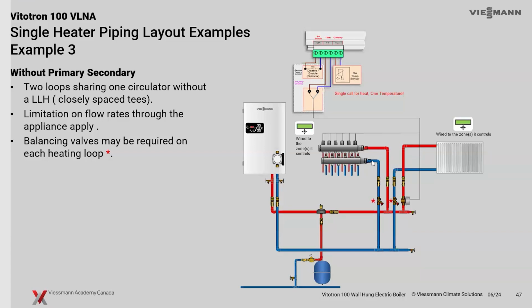If we were doing two temperatures here, the good point to remember is that we only have one set point on the boiler. So it's not going to give us multiple temperatures as far as our call for heat. If I had a radiant system here that required a lower supply temperature versus the panel rad, I'd put a thermostatic mixing valve in place to make sure that I didn't overheat that radiant system. But in this application, we're accepting the same temperatures on both of these styles of emitters.